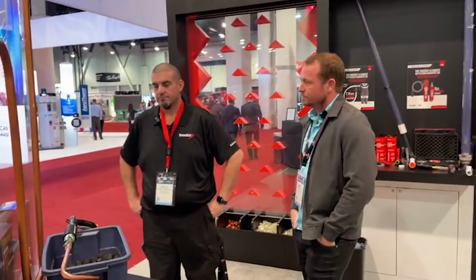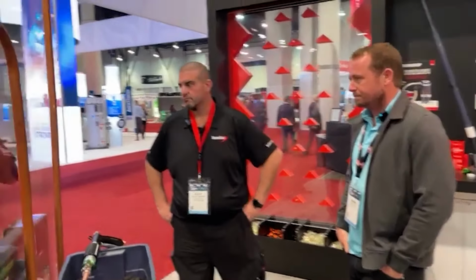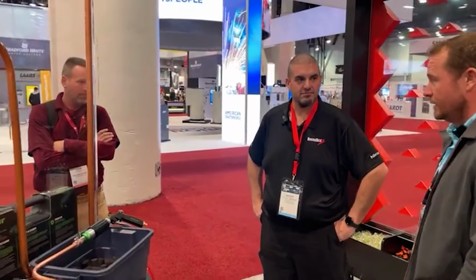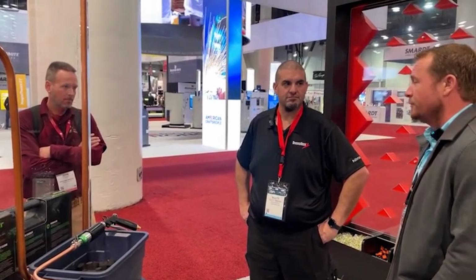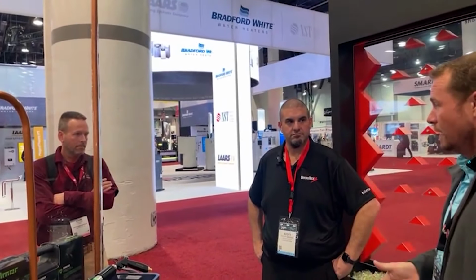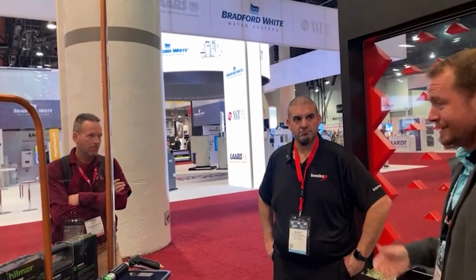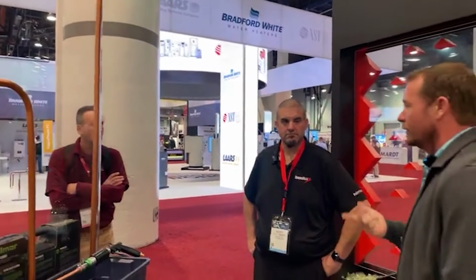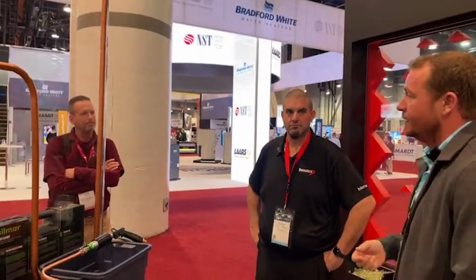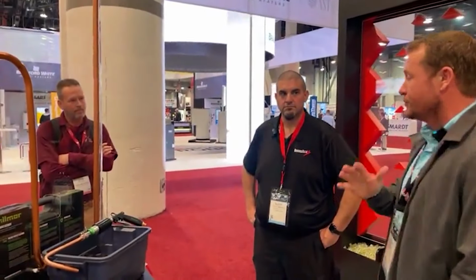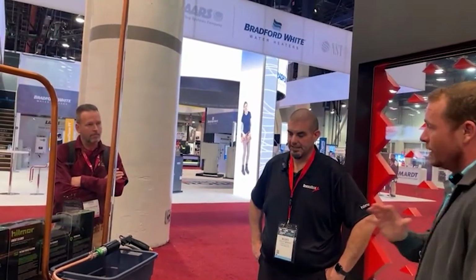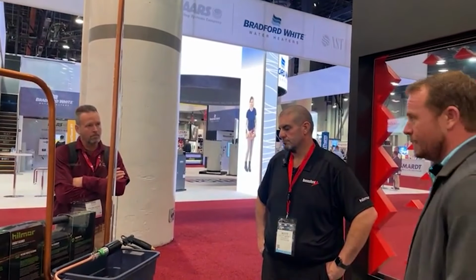We got a question. What about burnouts? We talked about that yesterday. What's that look like? If you have a burnout, this is an excellent application for this tool, especially if you've had multiple burnouts. You would need to cut the lines before you can push through. This isn't going to go through a manifold, a coil, a valve, or a line dryer, but if you've got a bad burnout and want to make sure the line set is completely cleared of burned out oil, this is an absolutely perfect application for it.